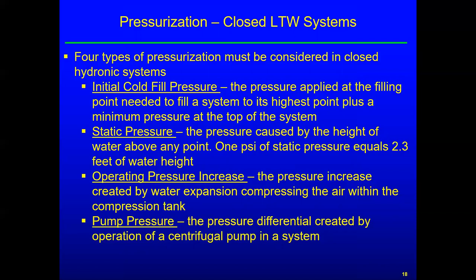The pump pressure is the pressure difference created by the operation of the pump. If I do all that and the pump's off, then I turn the pump on — what does that do to the pressure at the relief valve? We would like to design our system so that it doesn't affect it. But if I put the relief valve and that boiler on the discharge side of the pump, when I turn it on, the pressure jumps. If I do it wrong, every time we circulate the boiler, we drain water out of the relief valve. The devil's in the details.